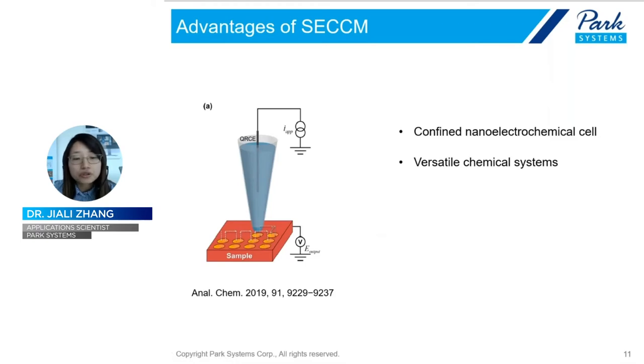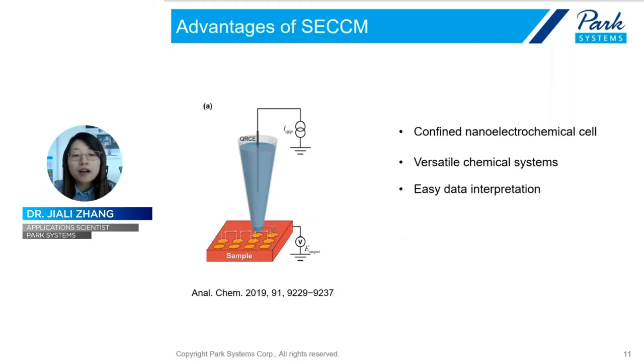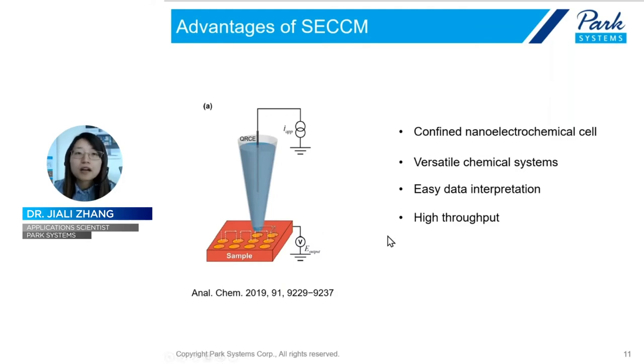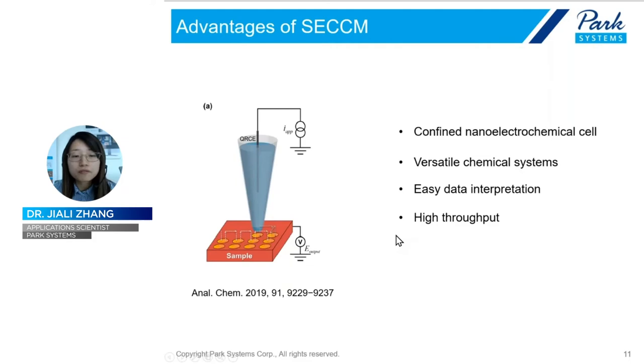The reason so many researchers choose SECCM for nanoscale electrochemical measurement is its unique advantages. First, the tiny meniscus droplet at the end of the pipette constitutes a confined nanoscopic electrochemical cell for nano-EC imaging. Second, researchers can freely choose the chemical systems they investigate by simply changing the composition of the solution filling the pipette, making it a versatile technique suitable for a variety of chemical systems with very little need for special sample preparation. Data interpretation is simple — higher current represents a higher rate of electrochemical reaction in the probed region. Each meniscus touch is considered a new experiment, making 10,000 experiments on one single sample possible, enabling high-throughput experimentation.